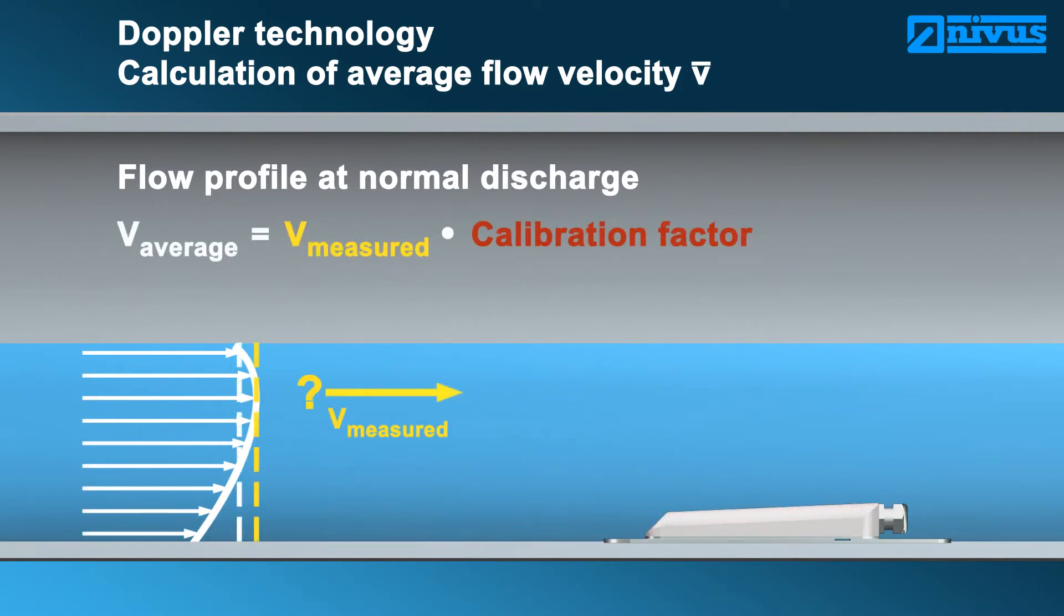To counteract this shortcoming, the average flow velocity is computed with the aid of a calibration factor. This factor must be determined previously, such as by implementing a grid measurement, which is fairly time-consuming and expensive.